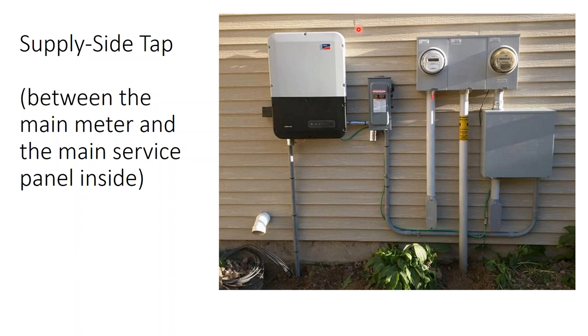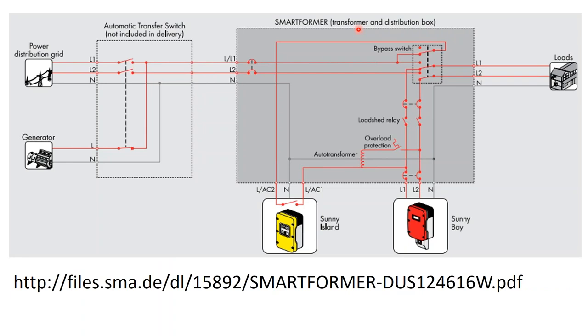So it has a separately derived output circuit that only comes on during a grid outage to draw a minimum amount of current through the inverter without batteries. It's pretty cool, pretty advanced. Whether or not that's a gimmick, whether or not that customer should actually be doing a battery system, that's a subject of debate. I think it makes economic sense to do the bare minimum today and kind of ride out the battery wave, especially with the recent changes in tax reform to the tax treatment of the credit.